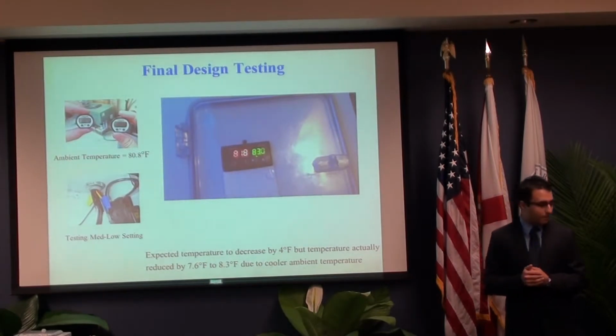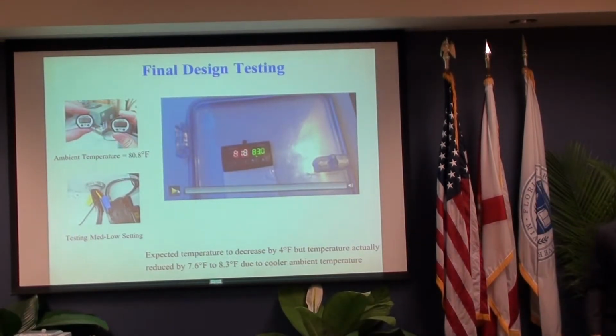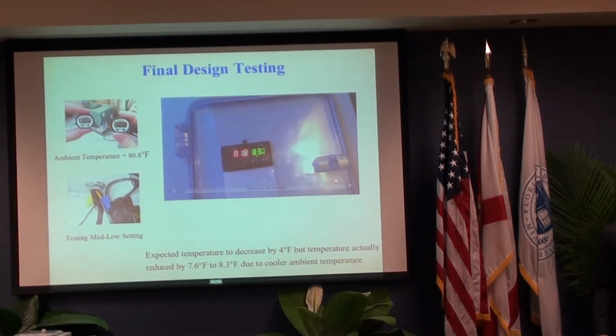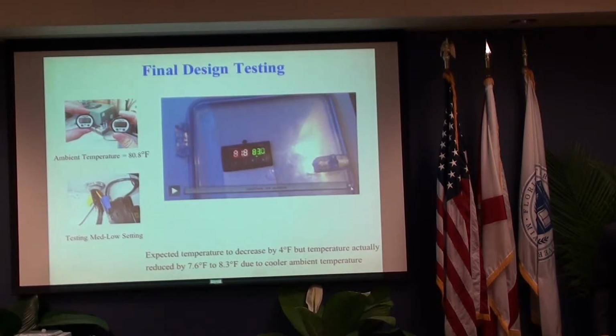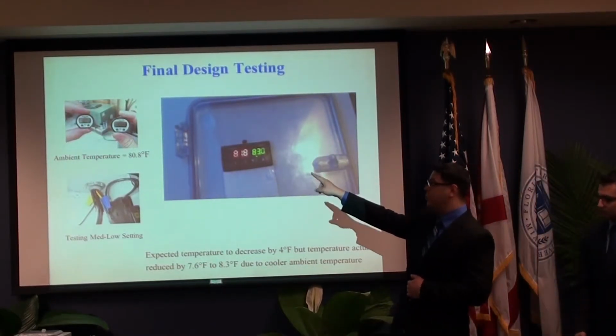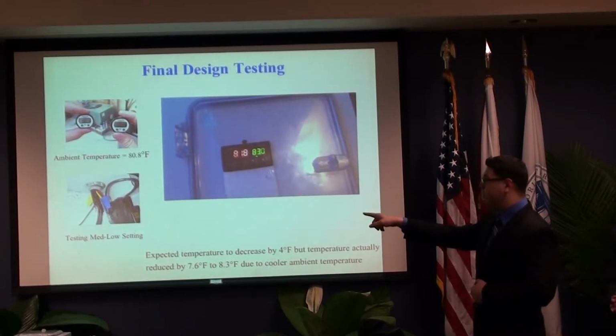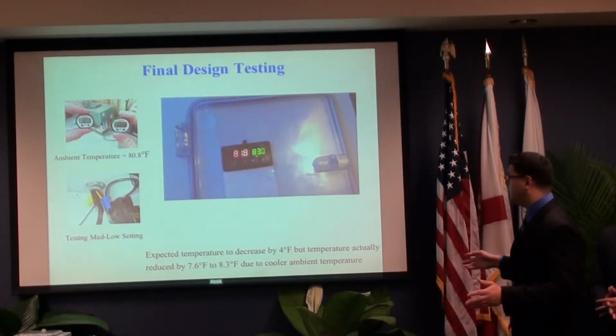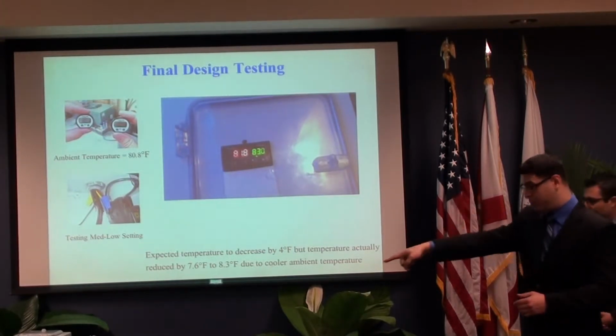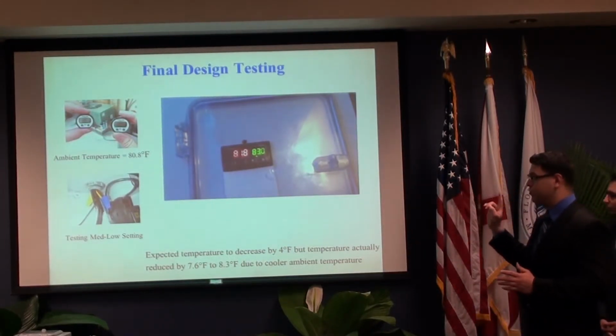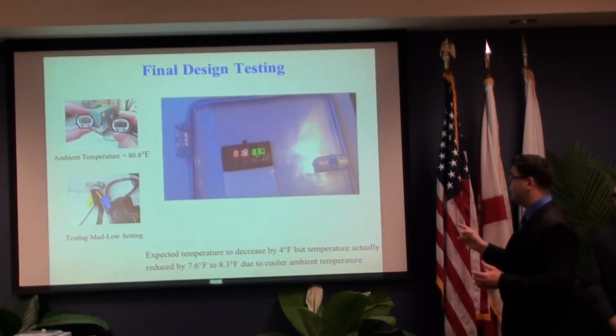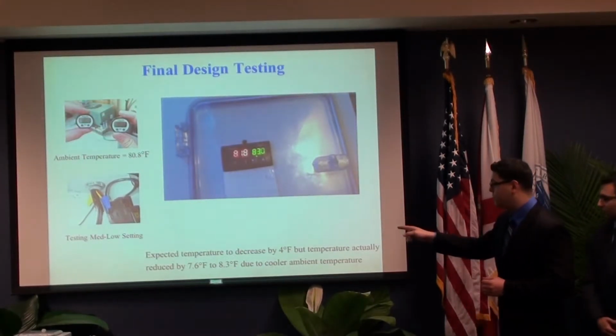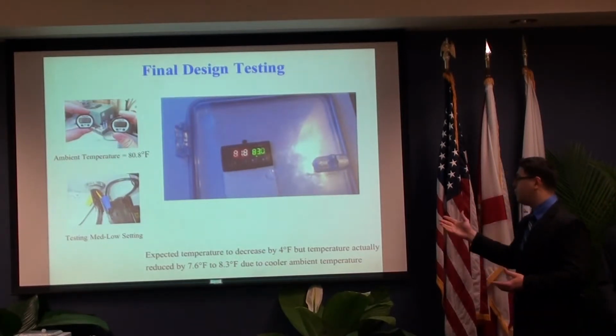So here we have a small demonstration of our cooling tower, the final prototype testing. As you can see, it's not working, but basically we have the ambient temperature of 80.8 degrees Fahrenheit at the top left, which you can see with the digital thermometers that we use. We're testing the medium-low setting so we can have a flow rate of 4,000 cubic feet per minute. And we were expecting this cooling tower, which is this one right here, to decrease 4 degrees Fahrenheit, but that didn't happen. It actually reduced it by 7.6 to 8.3 degrees Fahrenheit. And we know that it's because of the cooler ambient temperature.